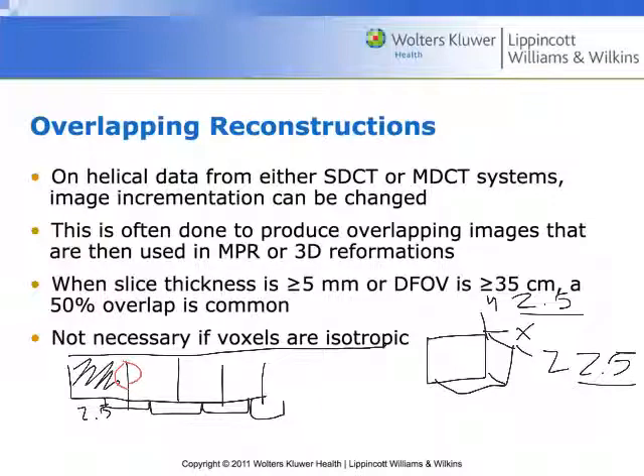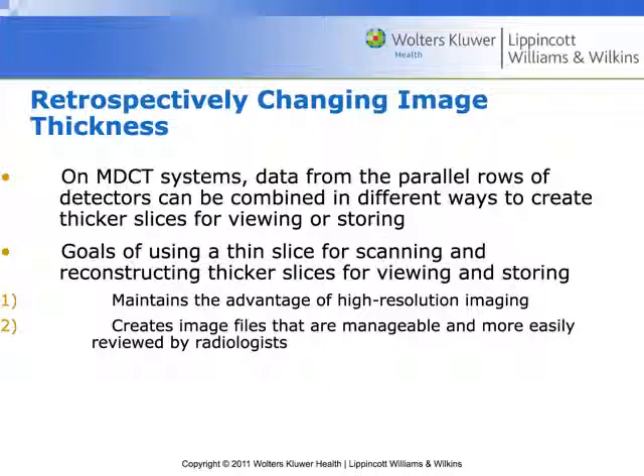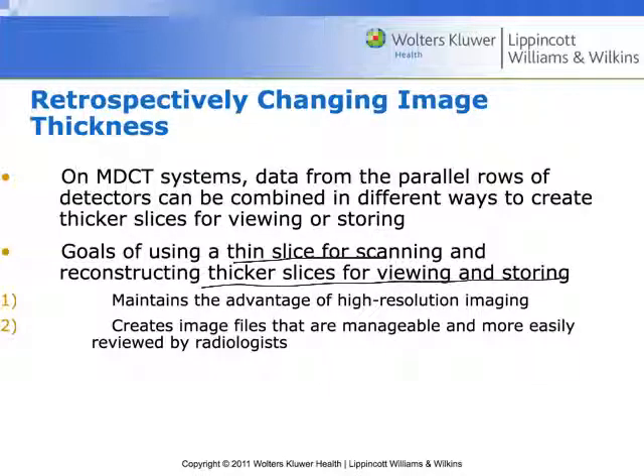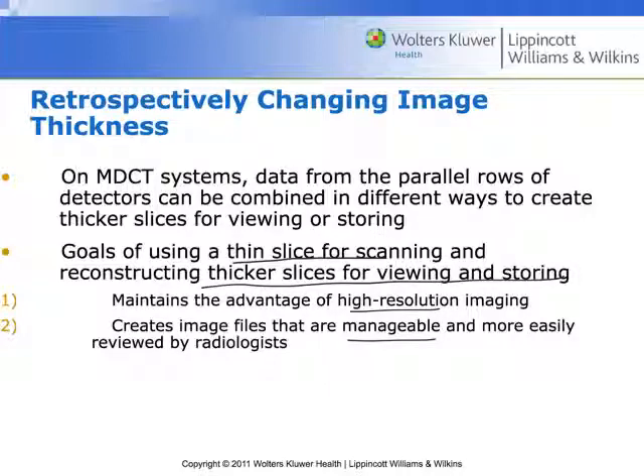We can retrospectively reformat the image to change the thickness of the slice, and that's precisely what we're doing when we do overlapping reconstruction. On a multi-detector system, the data from parallel rows of detectors can be combined — sometimes we use a thinner slice for scanning, but then we reconstruct at a thicker slice for viewing and storing. This maintains high resolution for the image and makes the workflow more manageable. Radiologists are seeing quite a few images — one institution I looked at had radiologists required to read or interpret an image every three to four seconds, so anything we can do to help manage that data volume they will appreciate.